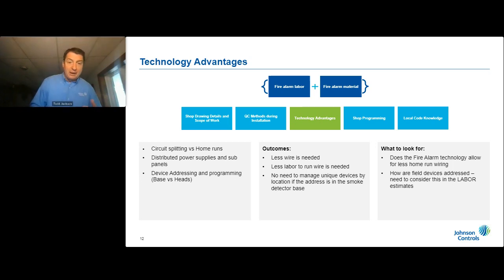You'll use less wire, you'll use less labor to run that wire, and depending on the addressability technology, you could carry a box of the same devices out to the field, and it doesn't matter which one you pull out of the box to snap into the fixture. Or, you're going to have to spend time labeling each device because the address is in that device, and you've got to put that device in the right place, or it's going to report incorrectly back to the panel.